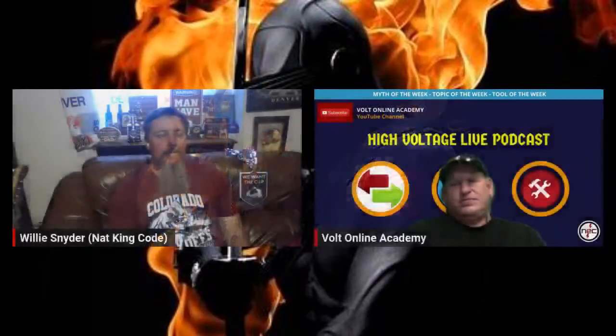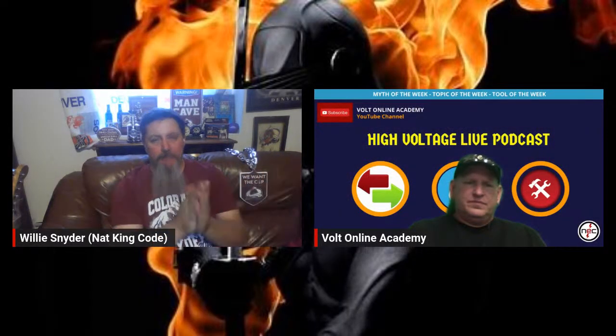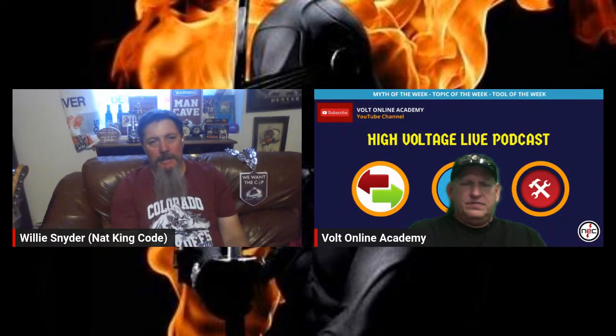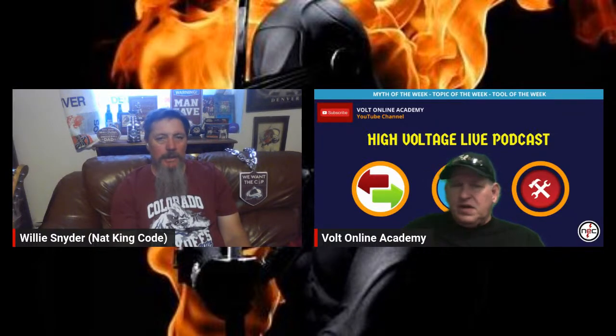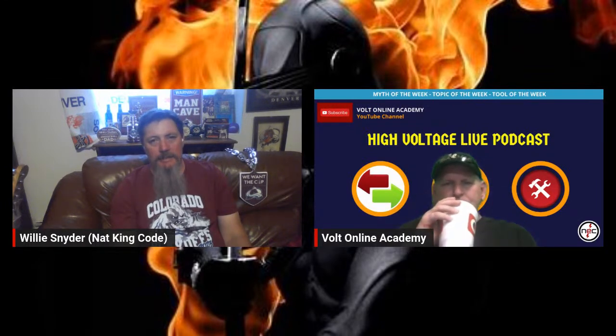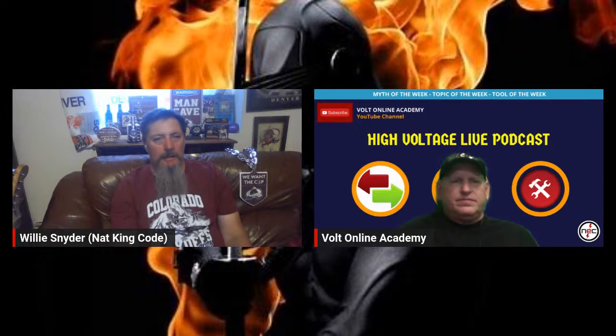I don't think this is just saying you can do a splice in a raceway. I don't think that's what this is saying at all. And just for everyone, this myth is busted, you cannot splice in a raceway underground. So basically that's what he did, he was trying to splice in a PVC that was going underground, my guess. He didn't say it was exactly PVC, could have been EMT, but it was some raceway that went underground, and they tried to splice about 12 inches just to get through, because they said the wire was stuck when they were trying to pull it. They said it wouldn't pull out, but they didn't have the right truck either, I could have gotten it out of there.